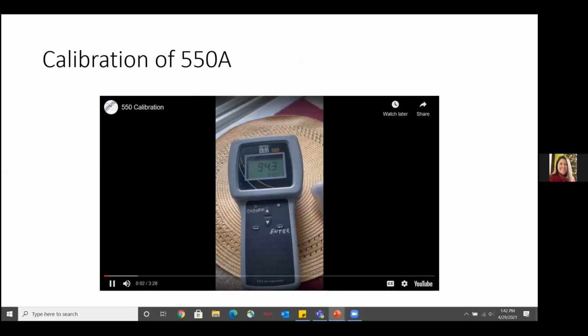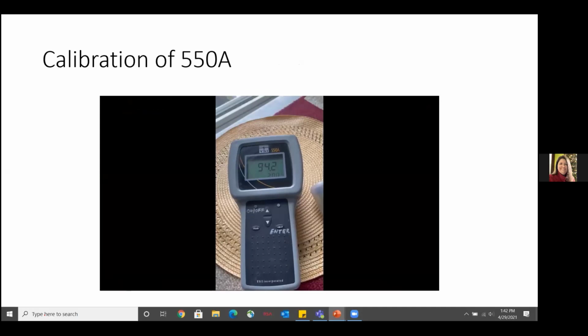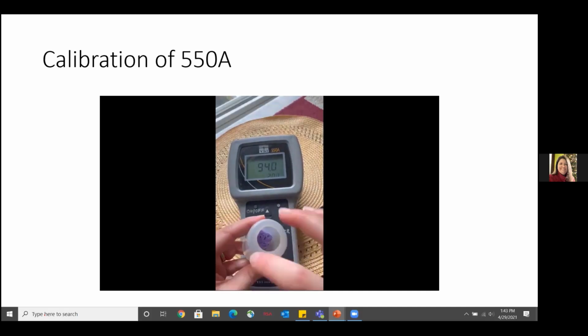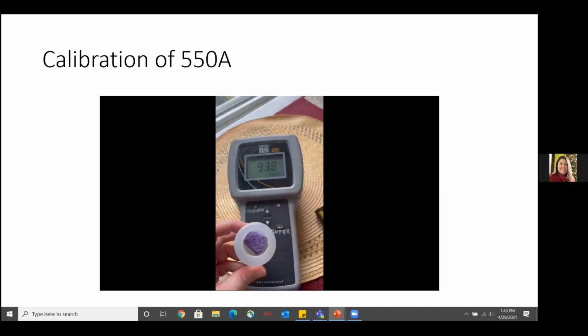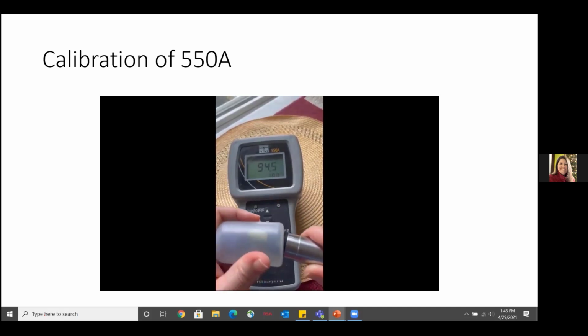Hello, this video is to show you how to calibrate your YSI 550A dissolved oxygen and temperature meter. If you have a YSI Pro 20, there's a separate video for that. The first thing to do is to turn on your unit and then let it set for about 15 minutes. I've already done that. The next thing you want to do is make sure that the sponge inside your probe cap is moist. There shouldn't be standing water, it just needs to be slightly wet. If it's dry, make sure you put a couple drops of water in there and then replace the cap.